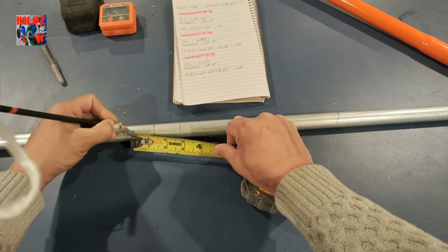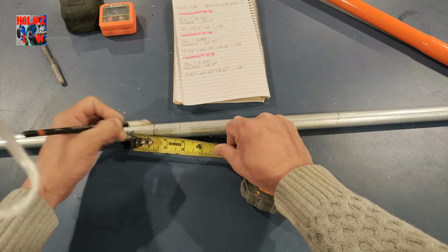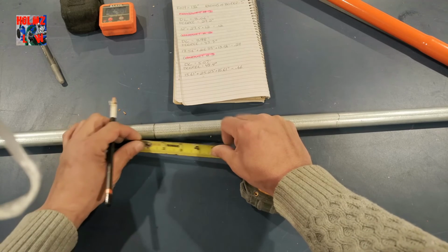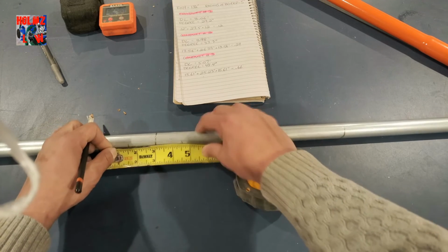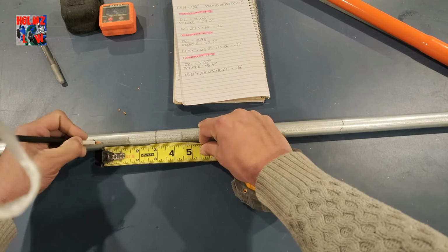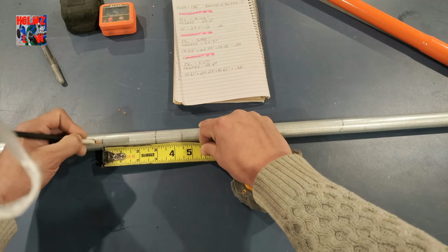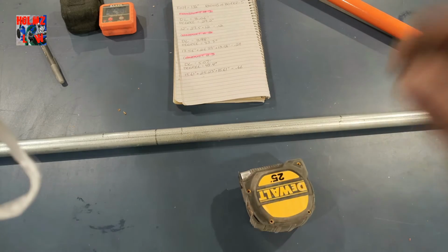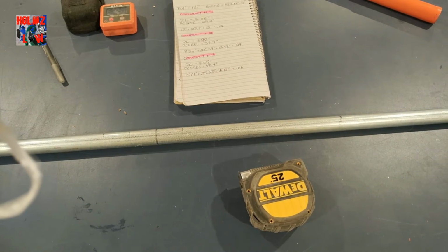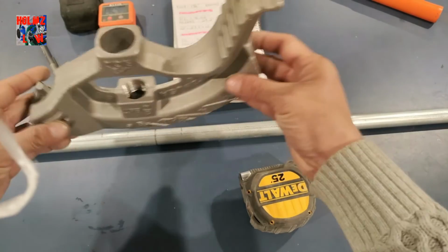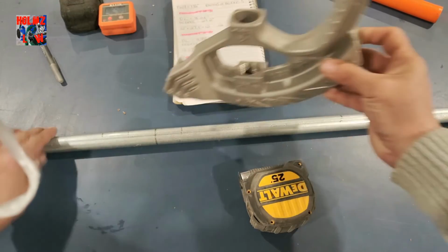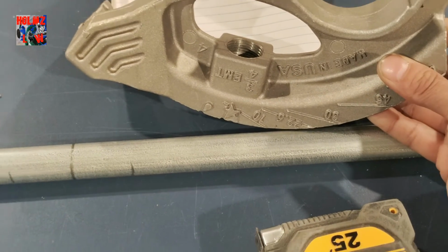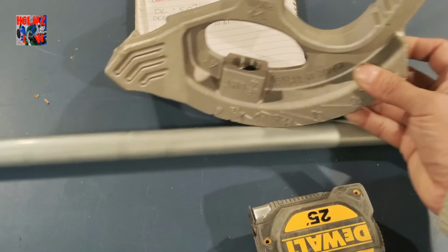So in order for me to get this bend directly on the center, I need to add my front of hook measurement. My front of hook measurement is also 1.5 inches, and I'm going to add that to my start of bend, which is going to be here. Give me a minute so I can show you. Sorry about that. Now, let me see if I can zoom in here. All right, that seems pretty good.